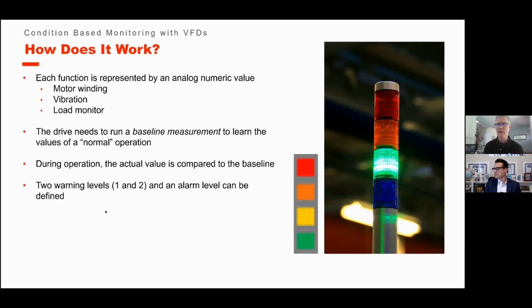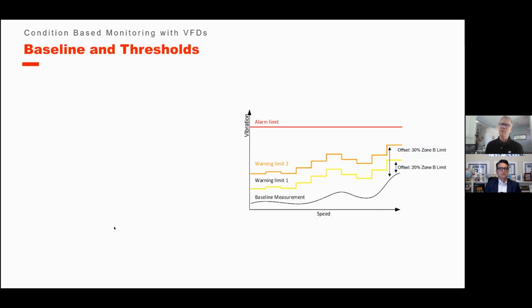What warning levels are relevant to that particular machine? So a little bit of machine knowledge is really critical. And we'll talk about some other things, but there's a little bit of setup involved with this. And of course, the indicators you see, if you do a remote access type thing, or if you're looking at the software while you're monitoring the values, you'll see the VDMA colors of green, yellow, orange, which is warning 2, and then red, which is fault. So it's kind of a universal color pattern, which is really nice. So baseline and thresholds, this is the brains really, and the heart and soul, I guess, of the software.